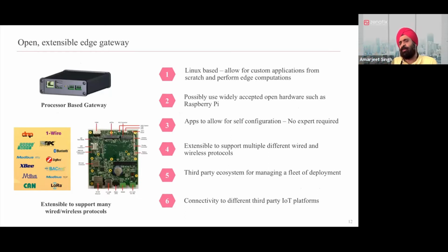But then somebody would say that, look, I already have traditional subsystems that come with their communication protocol, right? For example, I already have some Modbus based devices. I already have some BACnet enabled devices, etc., right? Can you connect to those existing devices as well, right? So that's where this gateway comes into the picture, right? Again, it's an open protocol based gateway built on Raspberry Pi. It's an industrial grade Raspberry Pi compute module, industrial grade hardware, and it comes with standard interfaces like RS485 and Ethernet, through which we can support Modbus over IP or BACnet over IP or even the SNMP protocol, right? So essentially, your traditional systems can then get connected via this gateway, and their data can also be pulled down.